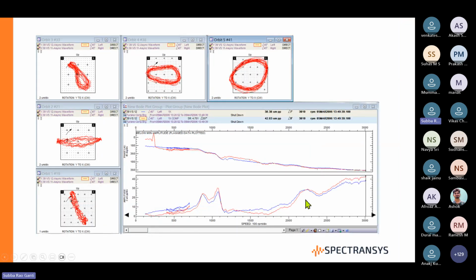So here I'm showing you a Bode plot of the machine shutdown. On the top you are seeing the orbits. On the left side, this is orbit 1, 2, 3, 4, and 5. Orbit 5 is captured when the machine is in the operating condition. You see a fairly circular orbit here, and at a certain speed in between, you can see that it slightly became elliptical. And these three orbits, orbits 3, 2, and 1, are captured at this critical speed event. You can see this is the split critical here, so one is the lower critical speed and the other is the higher critical speed.